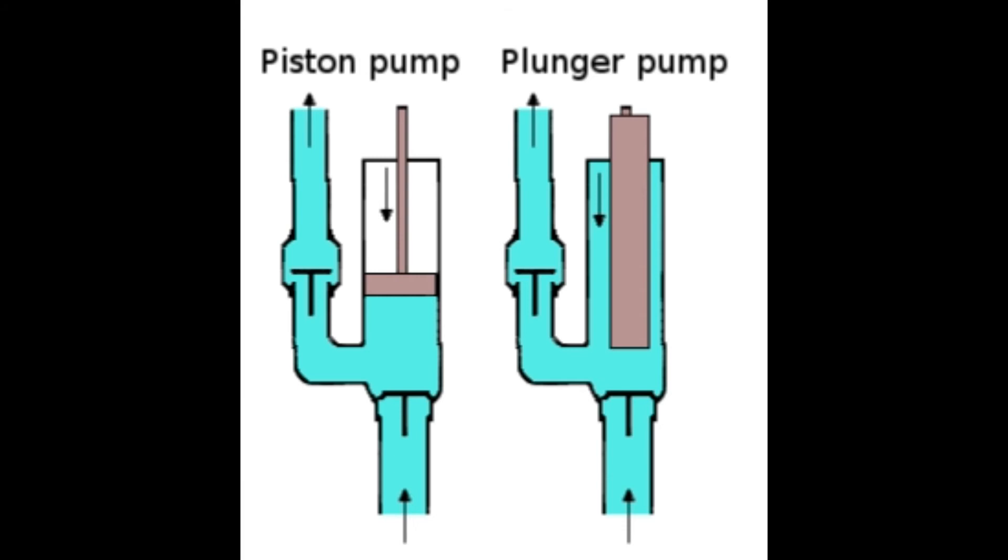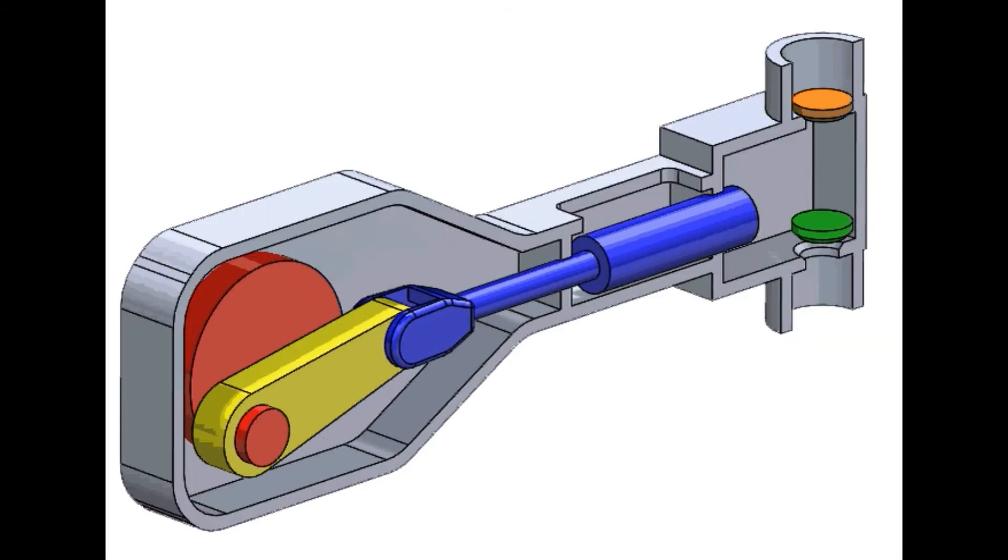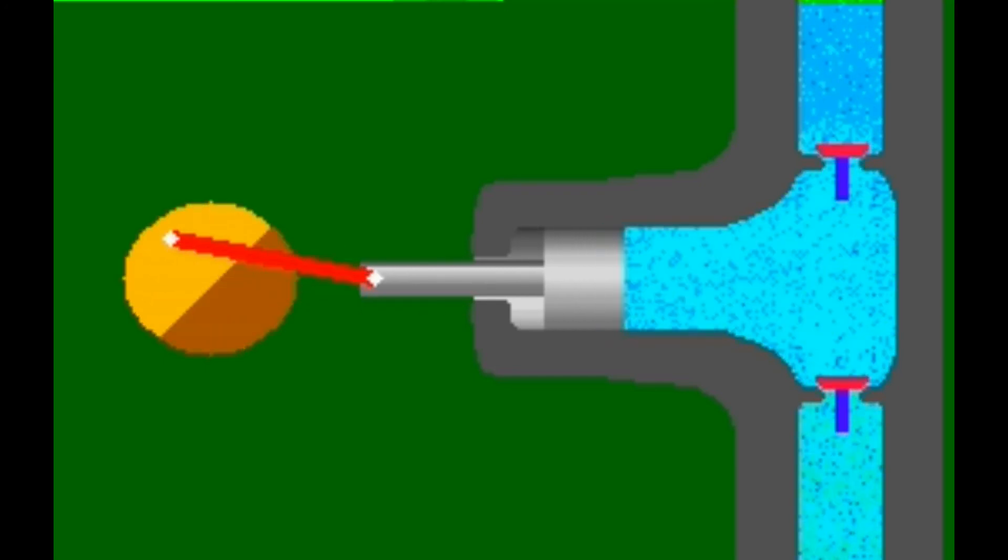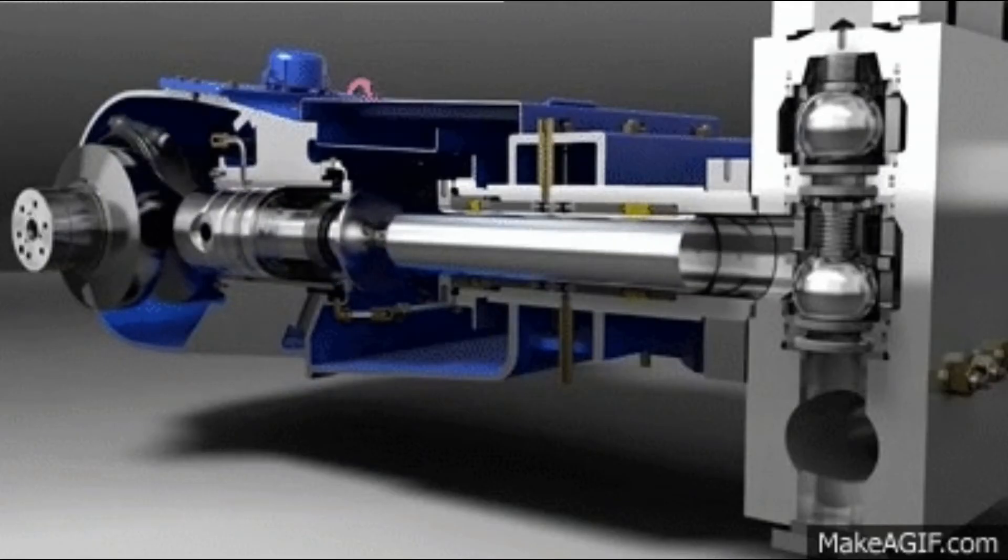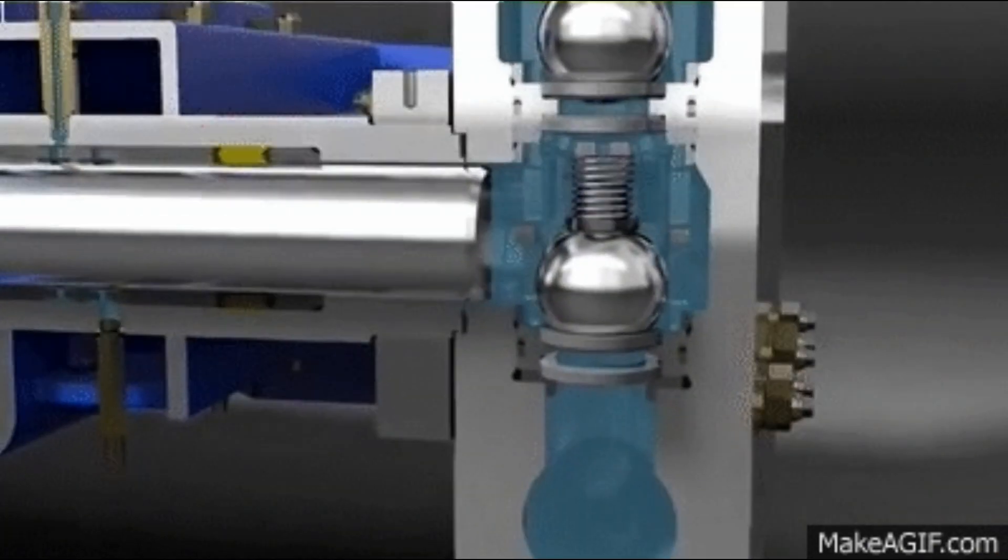What is a plunger pump? Plunger pumps are reciprocating positive displacement pumps. These consist of a cylinder with a reciprocating plunger. The suction and discharge valves are mounted in the head of the cylinder. In the suction stroke the plunger retracts and the suction valves open causing suction of fluid into the cylinder.